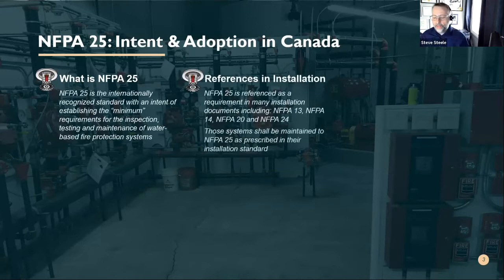This has come up in the past where we're not having the ability to use NFPA 25 directly. You can thread that needle by looking at installation standards like NFPA 13, 14, 20, and 24, which do reference NFPA 25. It's almost conditional for a new installation that it shall be maintained to NFPA 25, albeit the regulatory requirements are prescribed by the province.